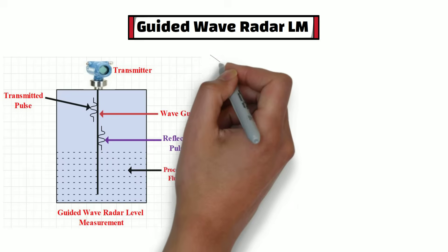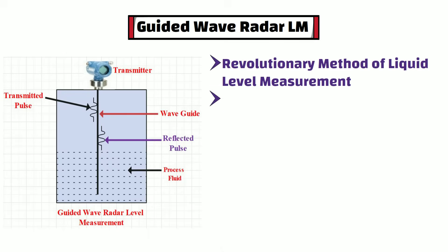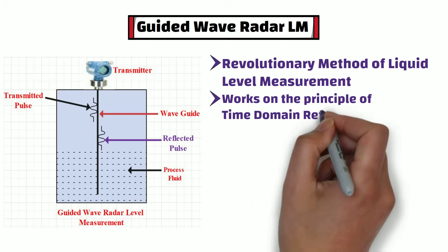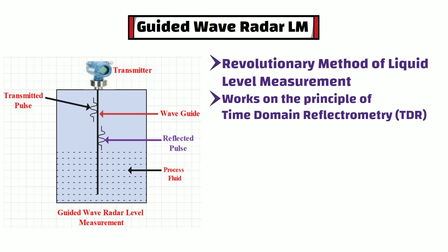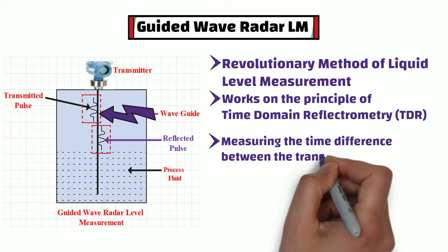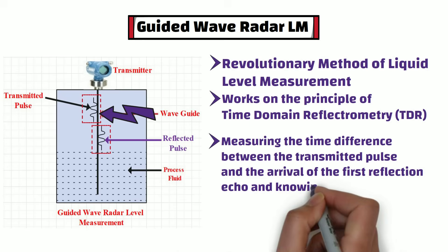The other type is guided wave radar level measurement. This is a revolutionary method of liquid level measurement, and it works on the principle of time domain reflectometry, also known as the TDR method. In the TDR method, a pulse is transmitted to the measurement vessel using a cable or rod. The pulse signal is reflected by the medium surface and received by the processing electronics. The distance of the reflecting surface can be calculated by measuring the time difference between the transmitted pulse and the arrival of the first reflection echo, and knowing the speed of light.